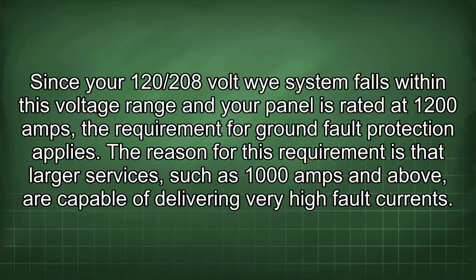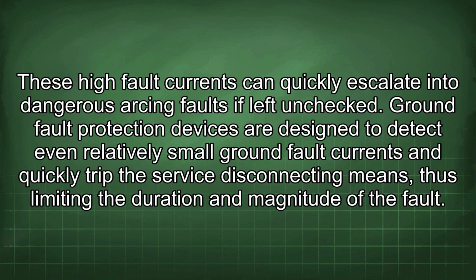ground fault protection applies. The reason for this requirement is that larger services, such as 1000 amps and above, are capable of delivering very high fault currents. These high fault currents can quickly escalate into dangerous arcing faults if left unchecked. Ground fault protection devices are designed to detect even relatively small ground fault currents and quickly trip the service disconnecting means, thus limiting the duration and magnitude of the fault.